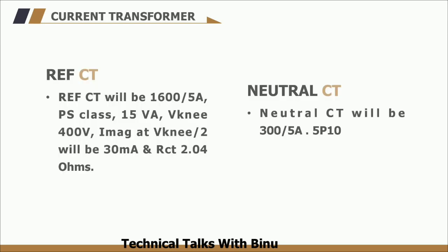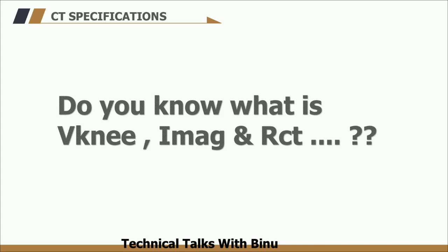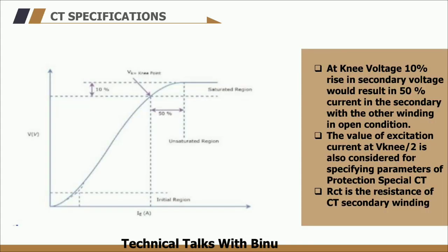The last parameter is the CT. Two CTs are provided in the transformer. The first is the REF CT, used to provide zone protection for the transformer. The parameters of the REF CT are: 1600/5A, PS class, 15VA, Vknee voltage equals 400 V, and magnetization current at Vknee/2 is 30 mA. The resistance of the CT secondary winding is 2.04 ohms. PS means Protection Special. Vknee voltage is defined as the voltage at which a 10% increase in secondary voltage would result in a 50% increase in secondary current.